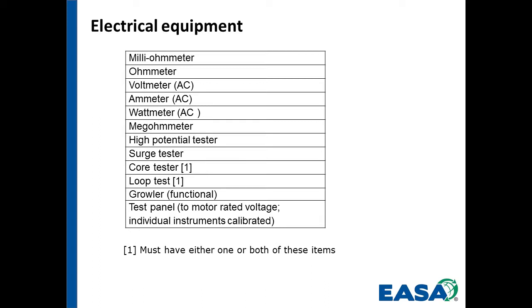You just magnetize something using a growler, so the growler doesn't have to have a calibrated ammeter. The test panel has to be good to the rated voltage of the motor that you're doing an accredited repair on. So if you have a 4,000 volt motor and your test panel only goes to 2,400 volt, then you couldn't accredit that repair unless there is the ability to outsource. If you could outsource it to a service center that could test run it and had calibrated instrumentation for that 4,000 volt rating and could run it at the 4,000 volt.